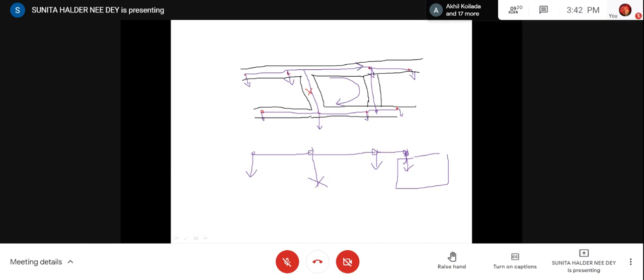Minimum potential point is where the current comes from both directions. Or, if it is the minimum potential point, either it will be fed from this point, or the current will be bifurcated from this point. So actually the philosophy is: the point around which the direction of current is reversed, that will be the minimum potential point. This theory is valid for ring main system.